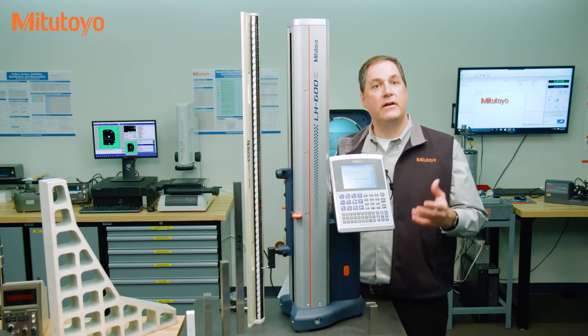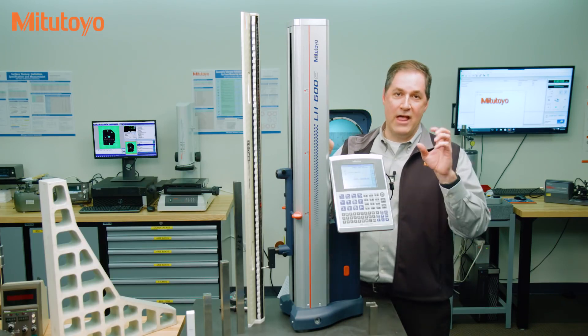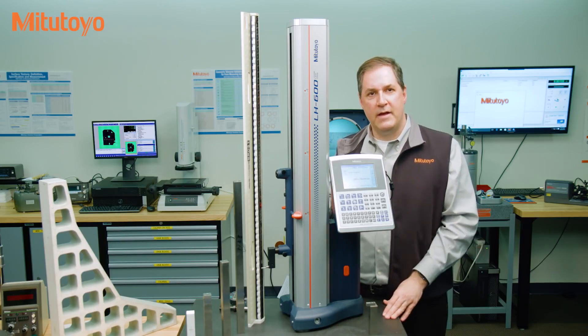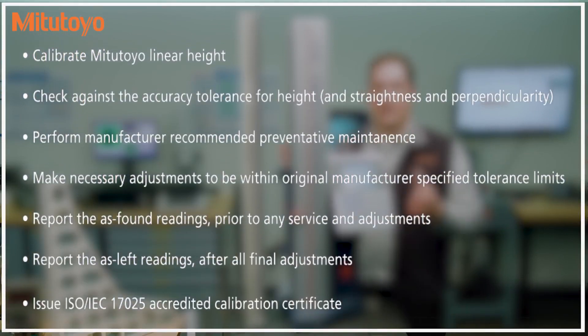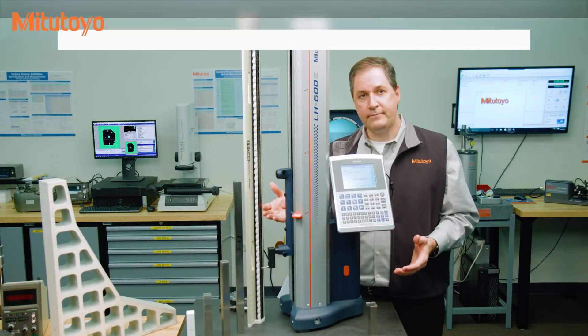If you are hiring somebody to do a calibration, protect yourself by being clear in your purchase orders. Don't just say, calibrate this gauge. As we often see in this business, instead, be more specific. Say something like, calibrate a Mitutoyo linear height. Check against the accuracy tolerance for height, and straightness and perpendicularity if you need that. Perform manufacturer recommended preventive maintenance. Make necessary adjustments to be within original manufacturer specified tolerance limits. Report the as-found readings prior to any service and adjustment. And then report the as-left readings after all the final adjustments. And finally issue an ISO IEC 17-025 accredited calibration certificate.